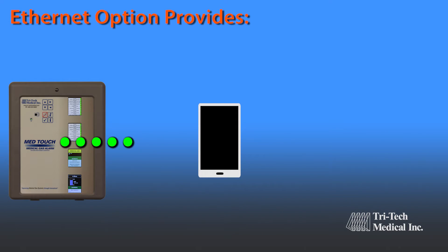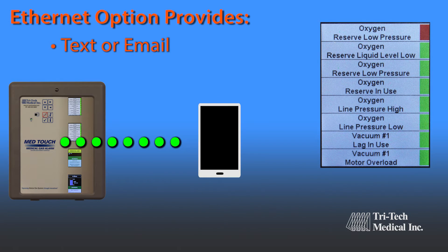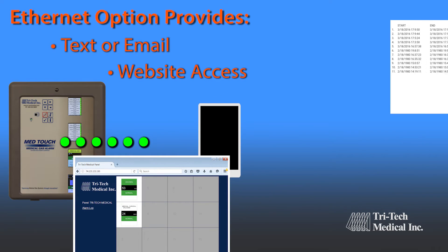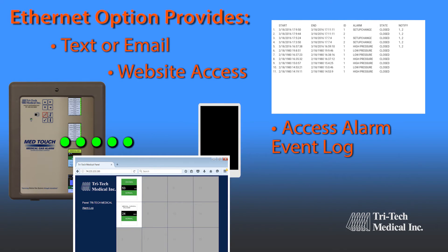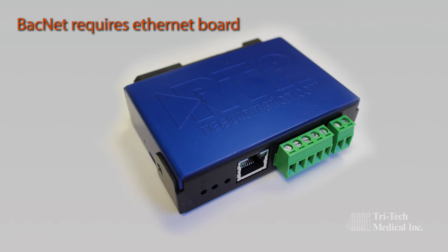Optional features include: the Ethernet option provides additional information directly to the user's mobile device, such as text or email notification of an alarm condition, website access to individual alarms to monitor current conditions, and access to the alarm event log. Also available are Modbus interface for all Tri-Tech Medical MedTouch series alarms, and optional BACnet interface.